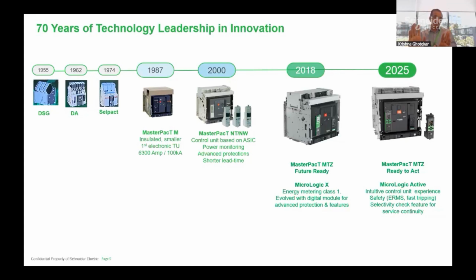Then we go with the MasterPact MTZ Active as the standard one, and MasterPact MTZ MicroLogic X is for the high-end application. So if I correlate with MasterPact NT and W, if it's a standard E type of trip unit, the basic one, the mirror of that is MasterPact MTZ with MicroLogic Active. If it is an NW with P and H, the higher trip unit, that mirrors into MasterPact MTZ with MicroLogic X type of trip unit. So you have a standard MTZ and an advanced MTZ range.